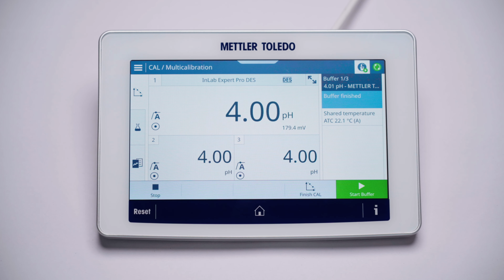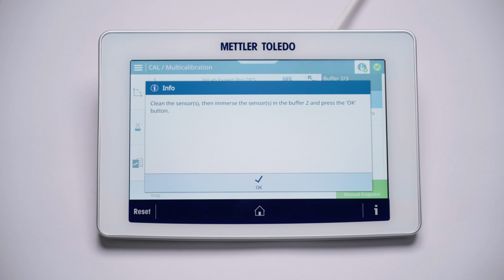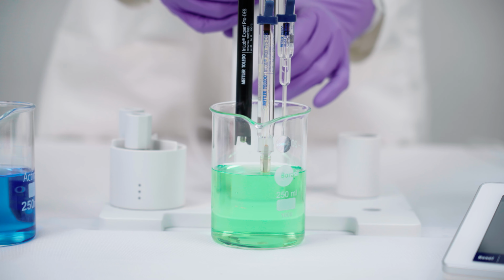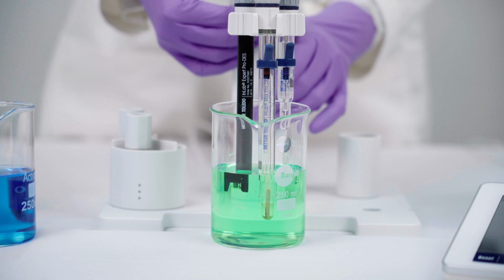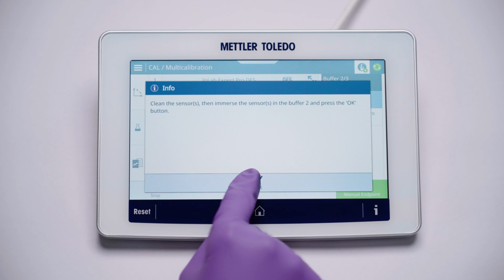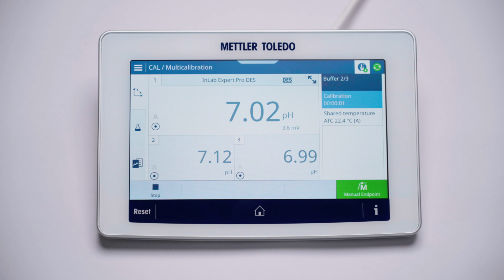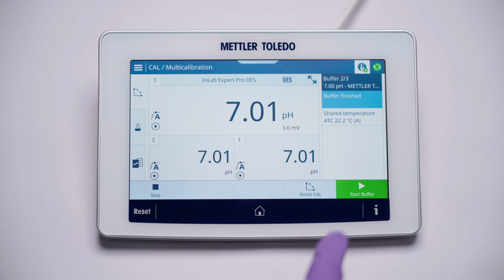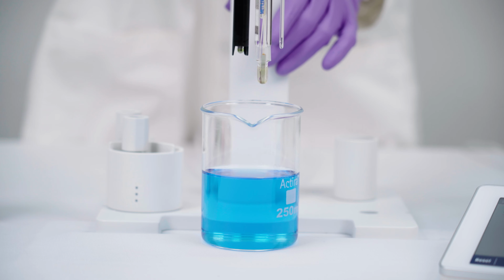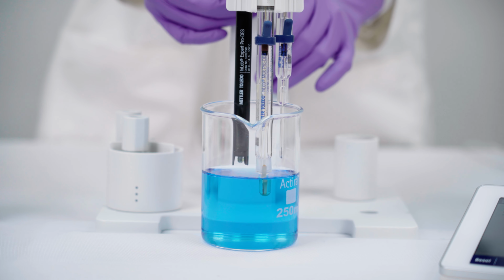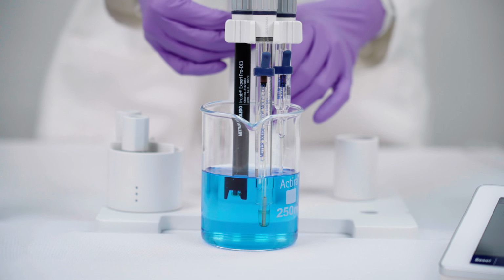Once the calibration with buffer 4.01 is done, click Start Buffer. After that, clean the sensors and immerse them in buffer 7.00. Confirm the sensor cleaning reminder message. Click on Start Buffer. Now clean and immerse the sensor in pH buffer 9.21.